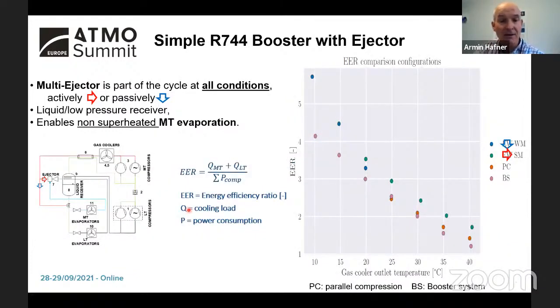It has been measured that we can outperform any other system. We see the basic standard booster system at the bottom. When we do parallel compression, we get an improvement, the higher the amount of flash gas we can remove. But you see, with this ejector system, we can really outperform and help to boost the seasonal efficiency in warm climates. Here is the gas cooler outlet temperature. Here we see the annual energy efficiency ratio, meaning with this kind of simple system, which is a traditional booster system a little bit reconfigured to be a low pressure receiver system, it is really possible to boost the energy efficiency and keep the system rather simple.